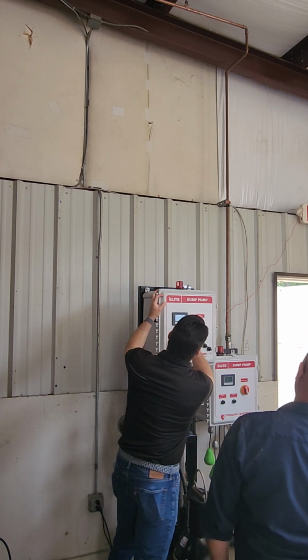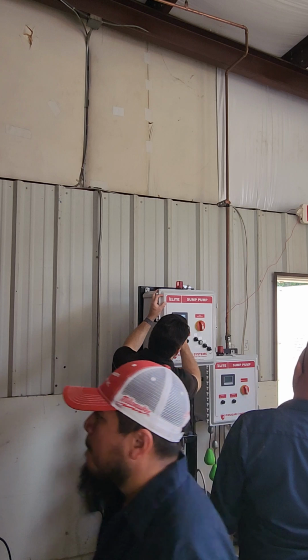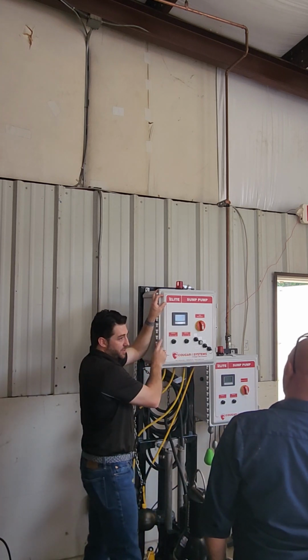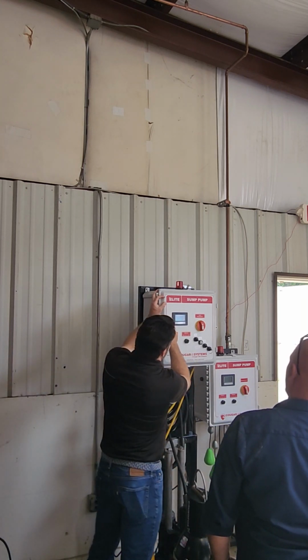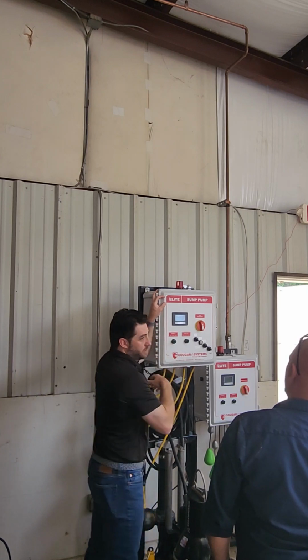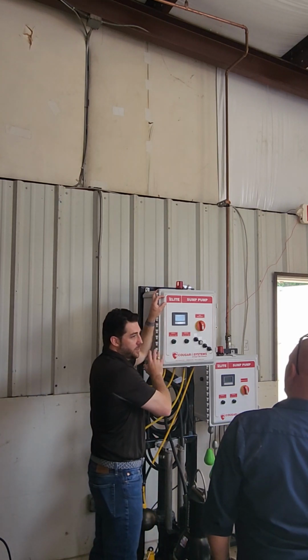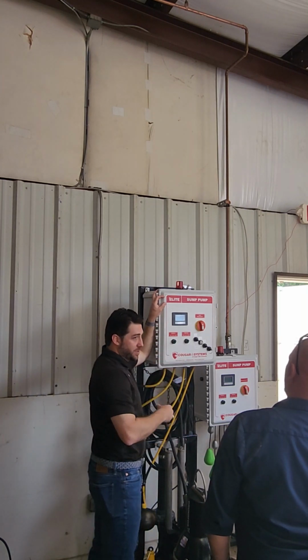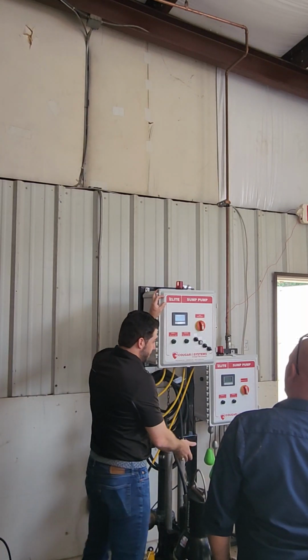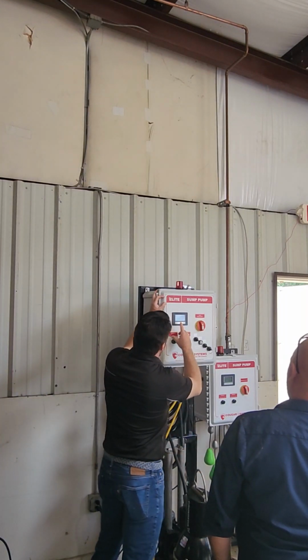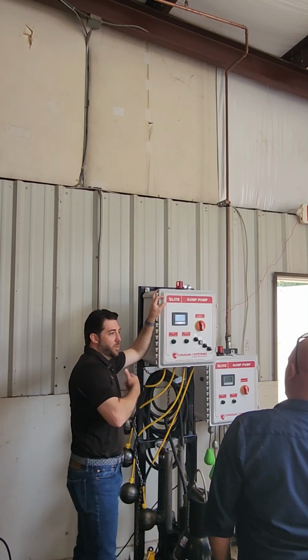If we jump into the settings, you got right here, so instead of having an alternating relay, you do it through the PLC to be able to choose if you want pump 1, pump 2 to be the lead, or if you leave it in auto. So you would leave it in auto unless you're doing service, and if you're servicing pump 2, then you would put pump 1 as the lead. That way it's always calling pump 1.